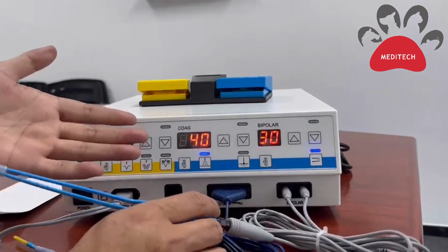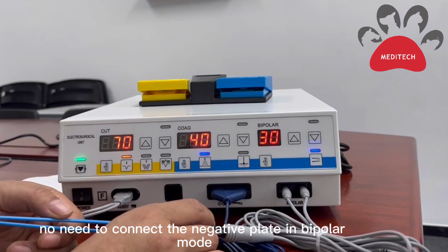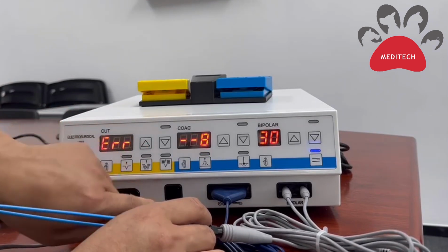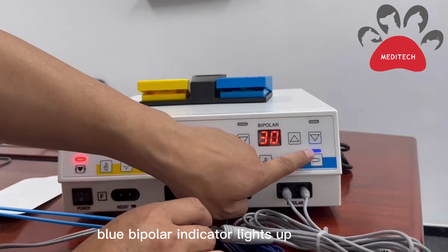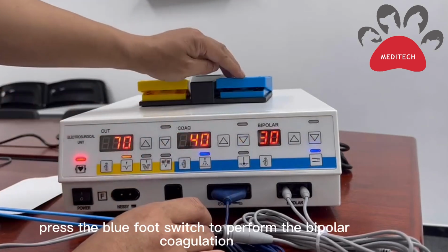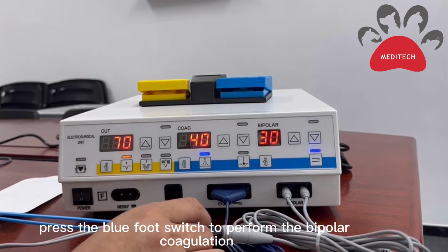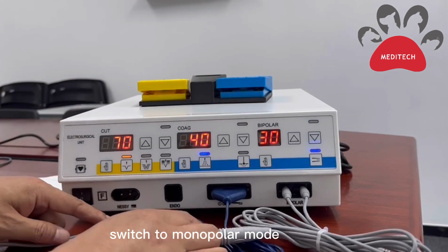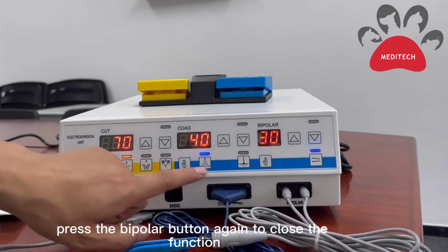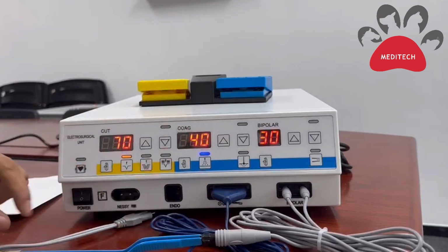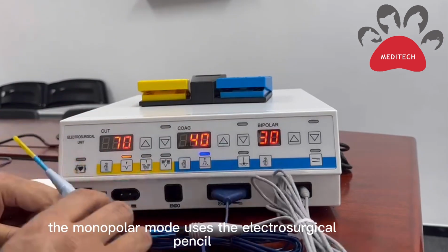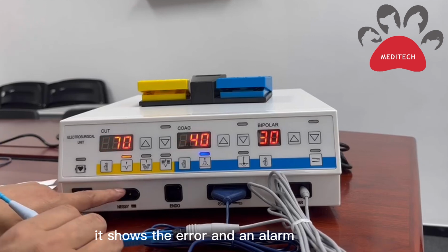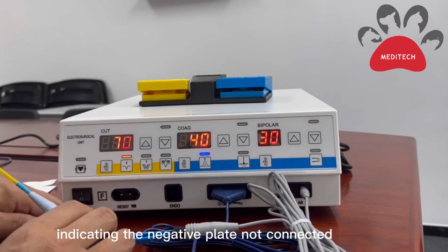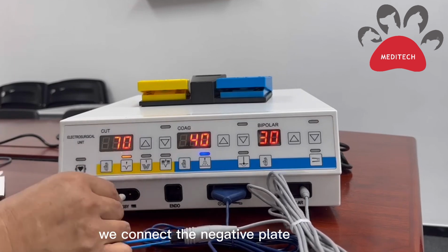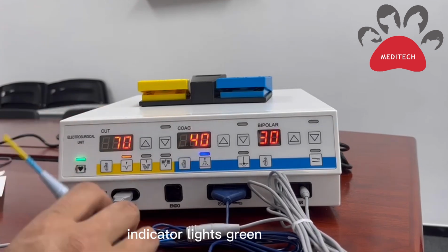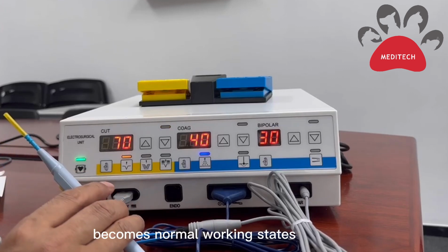Well, now we don't need to connect the negative plate in bipolar mode. Let's remove the negative plate. Switch to the bipolar mode. The blue bipolar indicator lights up. Press the blue foot switch to perform the bipolar coagulation. Switch to monopolar mode. Press the bipolar button again to close the function. The monopolar mode uses the electrosurgical pencil. It shows the error and an alarm, indicating the negative plate is not connected. We connect the negative plate. The indicator light and screen become normal working states.